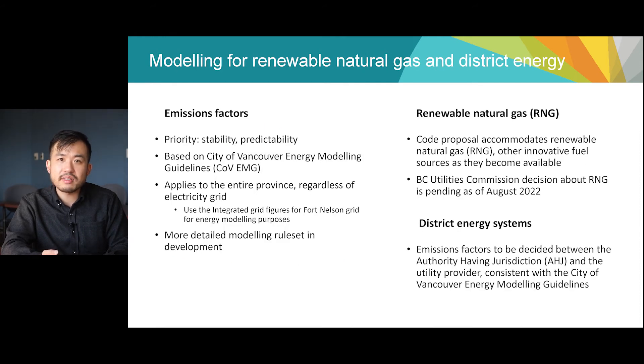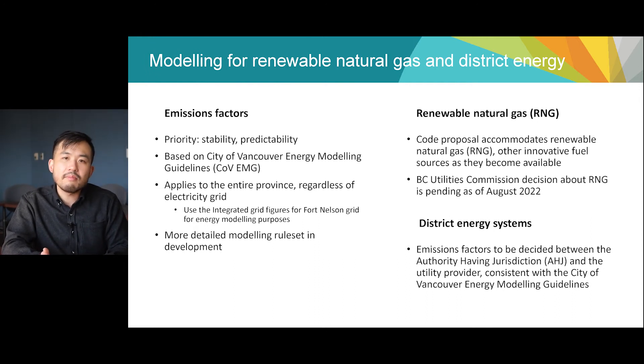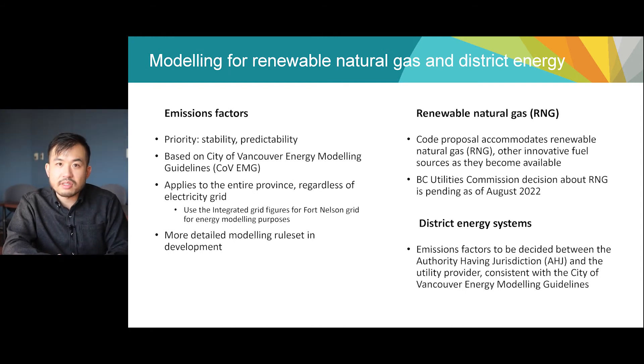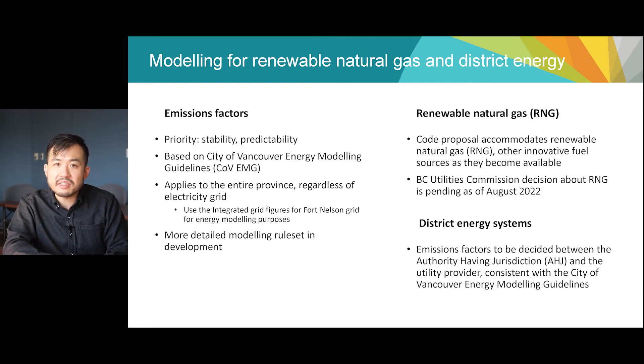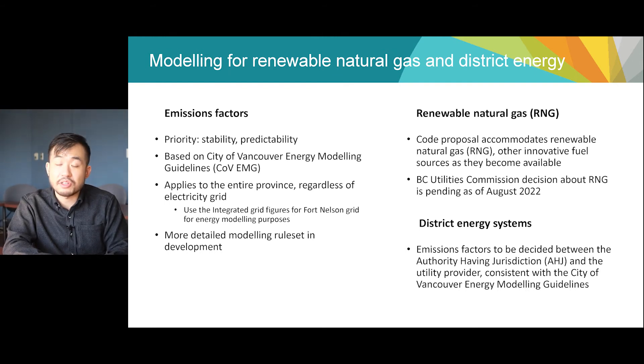Measuring carbon emissions from buildings requires a set of energy modeling guidelines which describe how emissions-intensive each energy source is — in other words, it assigns an emissions factor for every unit of energy, for example 0.011 kilograms of CO2e per kilowatt hour. These factors are a snapshot in time and are a sophisticated estimate, but don't always reflect the true emissions of an energy source because emissions can fluctuate. For example, most electricity consumers in BC are connected to the integrated electricity grid, which is supplied mostly by hydroelectricity and is at least 93% clean by legislation. However, there are times when emissions change if the utility purchases higher carbon energy to supplement the hydroelectricity supply. Although there are plans to make the integrated grid 100% clean in coming years, the emissions factor still fluctuates as of August 2022.